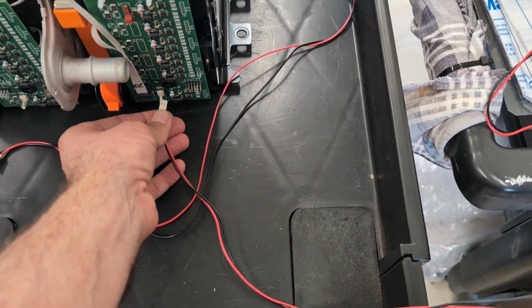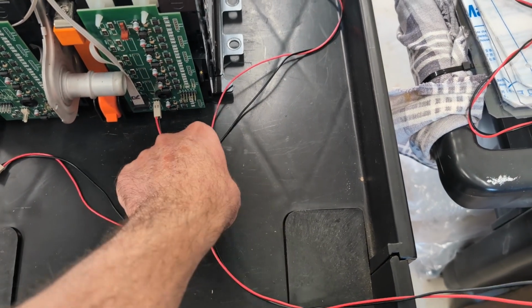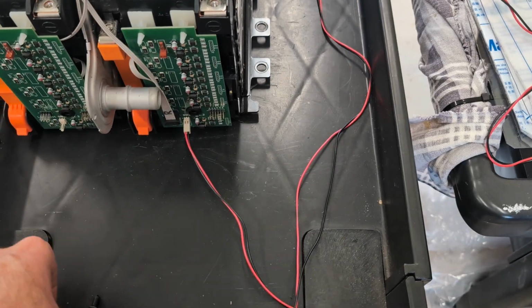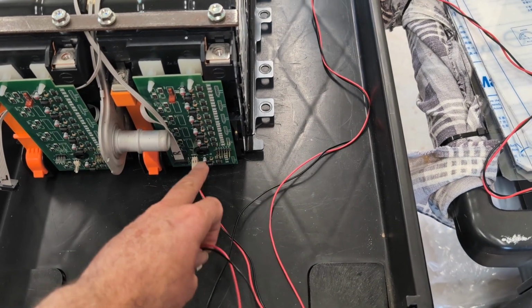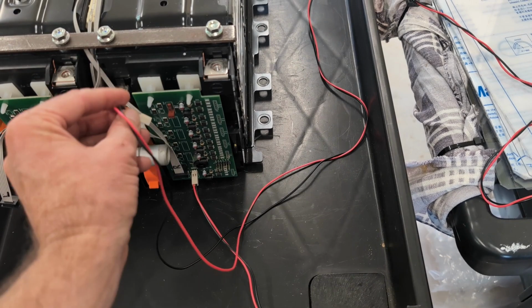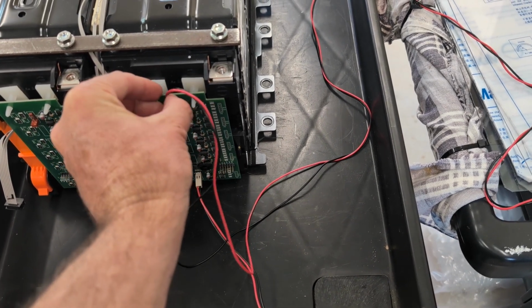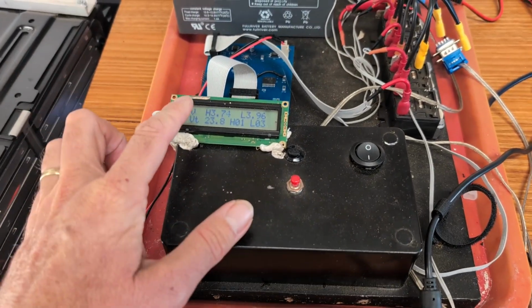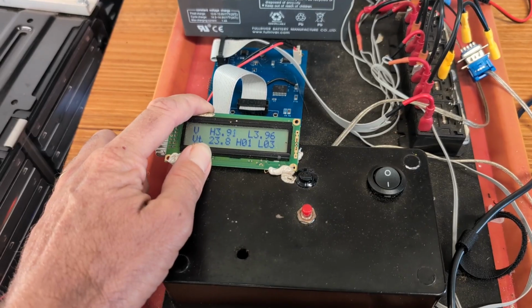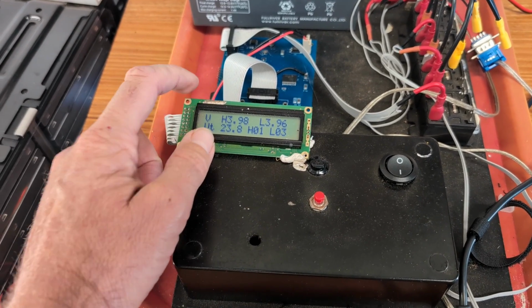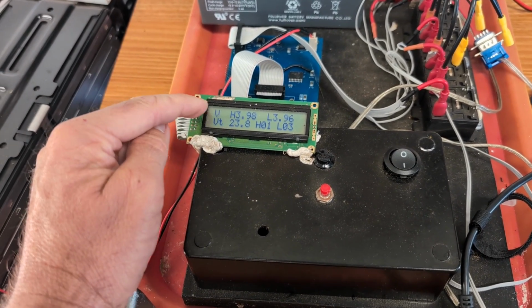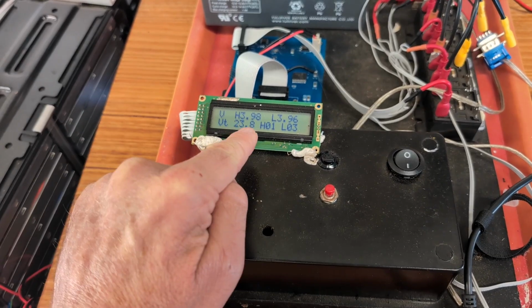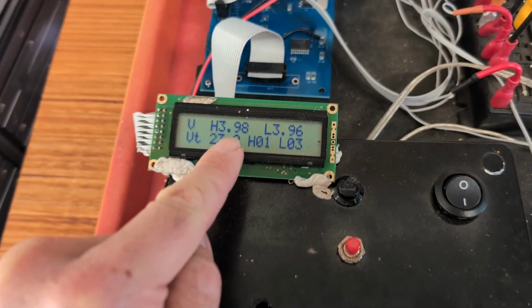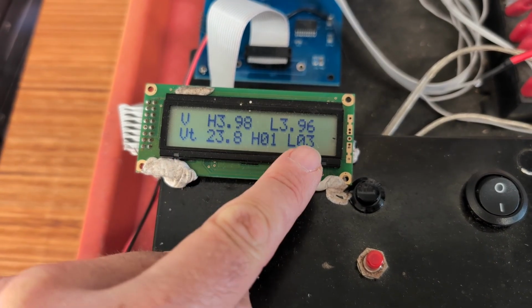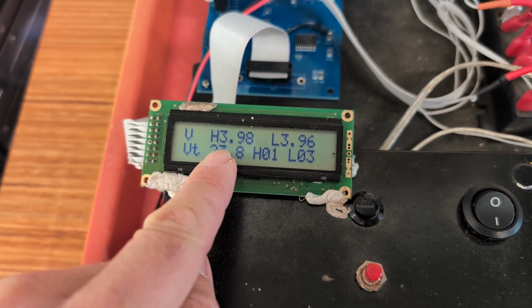So the output from the master goes into the input of the first module circuit board, and then they all talk to each other and it comes out finally here, and this one goes back to the input of here. You heard a click. That's because the master here has figured something out. So it is now showing the voltage of each cell here. So the voltage of the highest cell and the lowest cell is what this is showing. So it's now gone from 3.96 to 3.98.